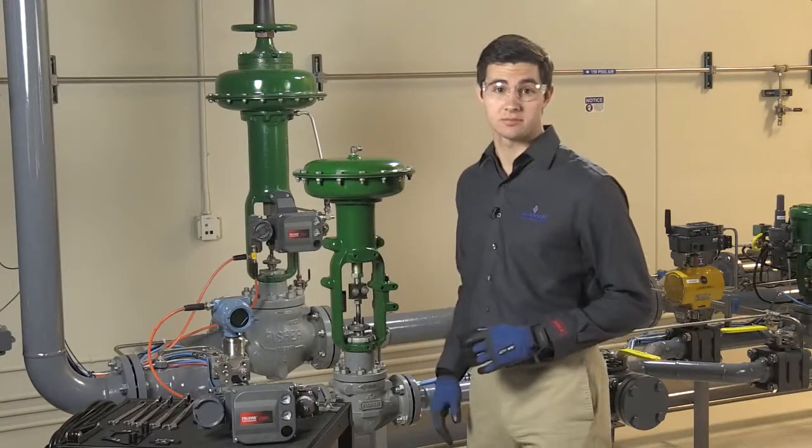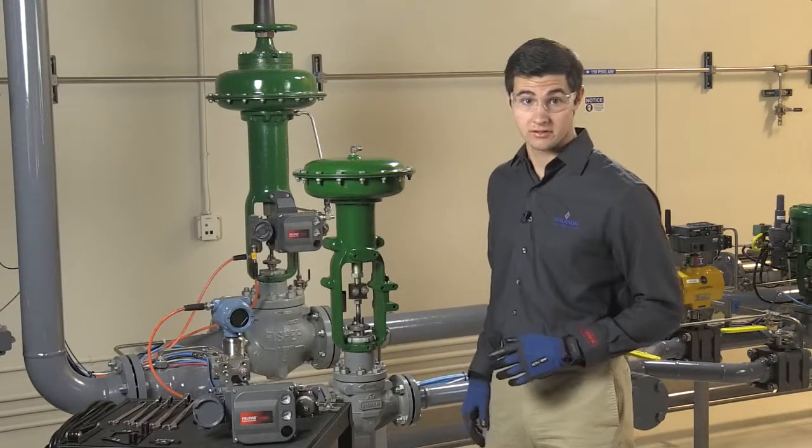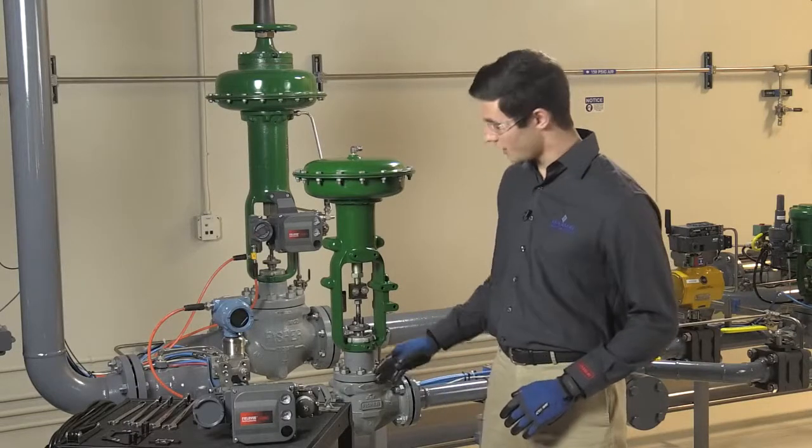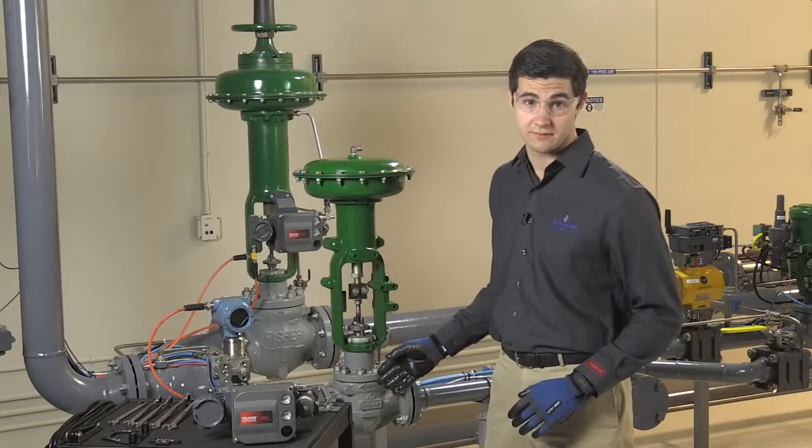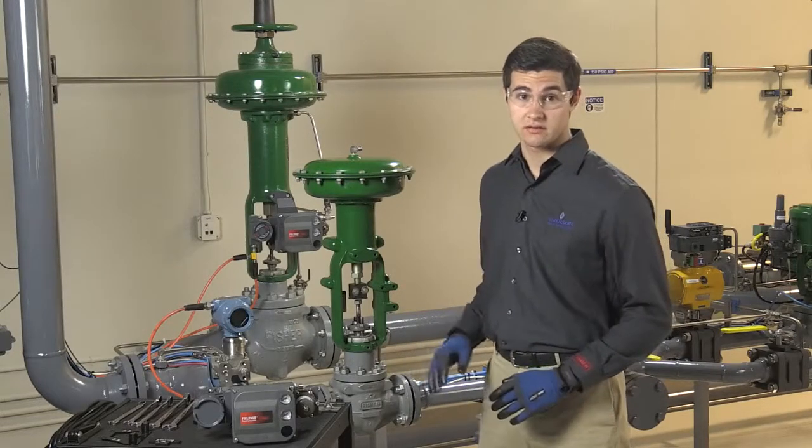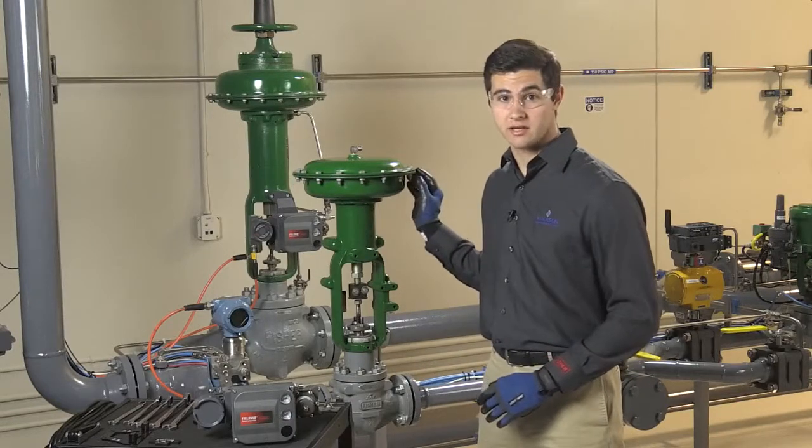Now, we need to take two precautions before proceeding. First, completely isolate the valve and actuator from the process if it's in service. Second, relieve all the pressure in the actuator.